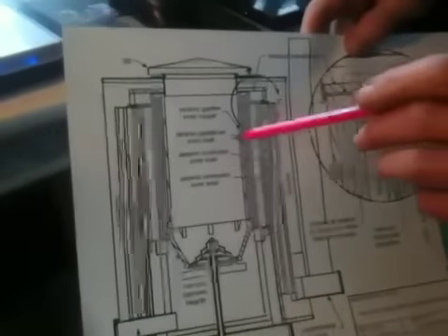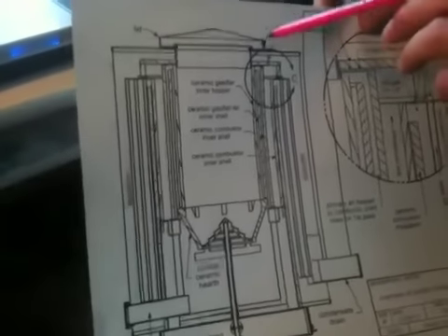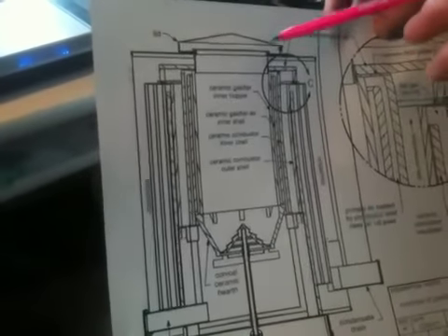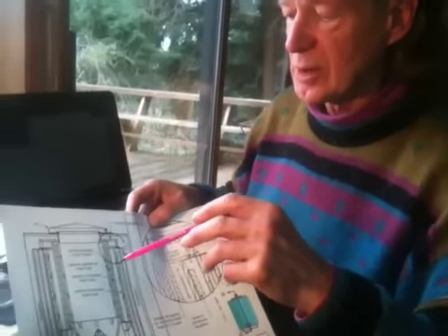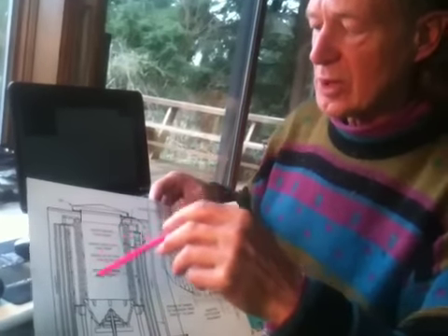So we have the hopper here where the fuel is put in through the lid on the top. It's a double seal because where you have gasification, you have pyrolysis of the fuel, and it's different from the normal wood stove that blends all the processes together of gasification, combustion, and heat exchange. So you have the sealed hopper here with the fuel on it, and that can be extended up to incorporate as much fuel as you want.